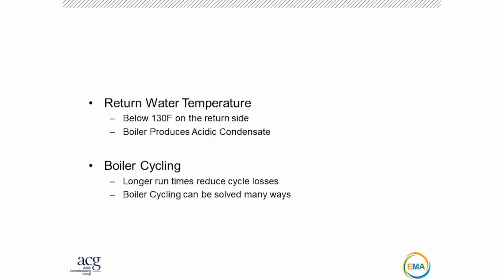I mentioned it earlier. It's the dew point of the flue gases, right? It's in the ballpark of 130 degree water on your return, right? So your boiler's supplying hot water out. It's coming back colder because it gave up BTUs to the building. If that return is about 130 or colder, you'll start to condense. Now there's more to it than that. There's things like how much excess oxygen is in the combustion process, right? If you have too much oxygen, you'll lower that dew point. Right now it might be 120 or 110 or 100, which makes it harder to condense, right? You want the dew point to be higher so that you can condense more often, which will make you more efficient more of the time. But that's really one of the keys, return water temp.